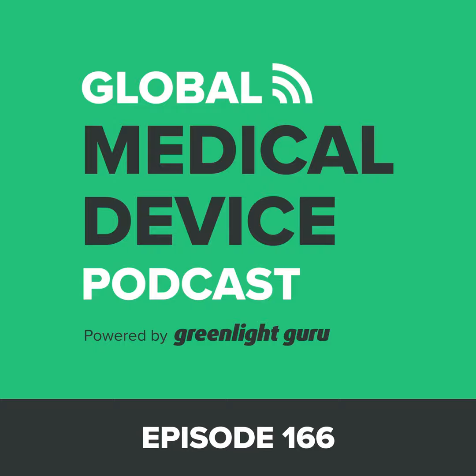Just one or two other suggestions about the guidance. FDA says that sponsors should document how they've determined biocompatibility risks and where biocompatibility testing is not necessary. And again, to me, this is a no-brainer. This is something that I've been doing for the nearly 30 years I've been playing this game. However, they go on to give some examples.